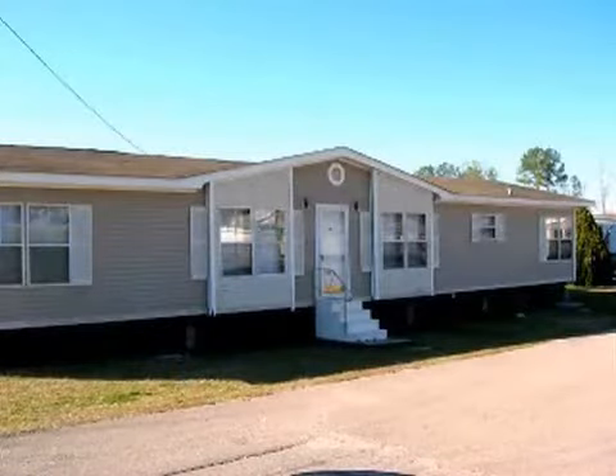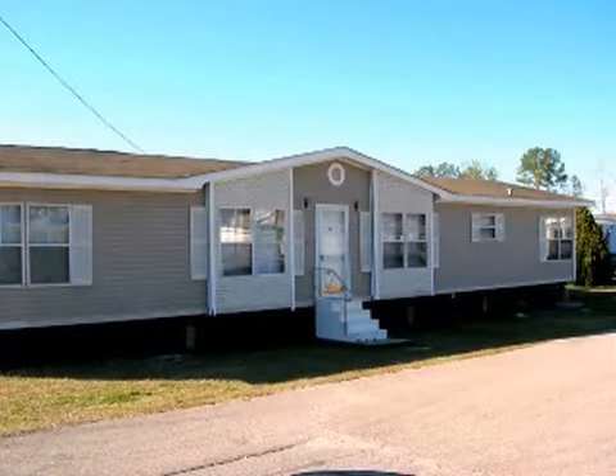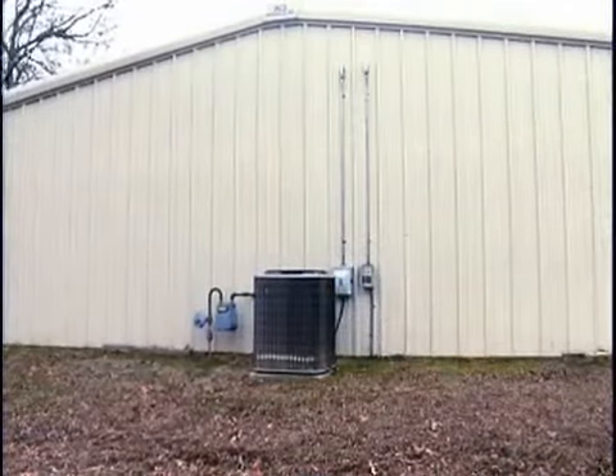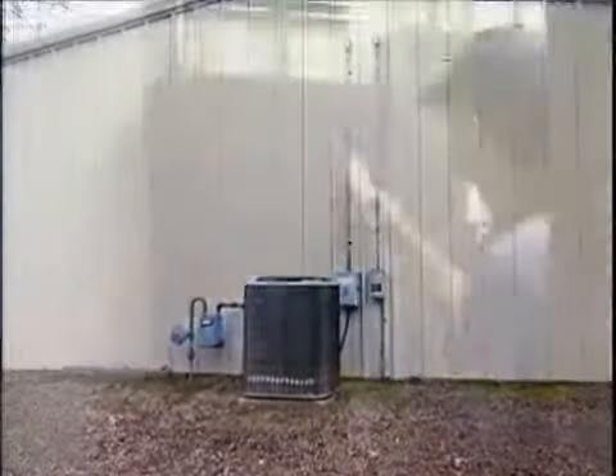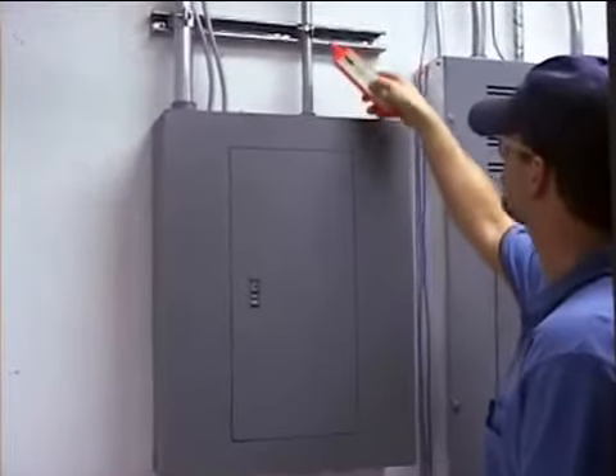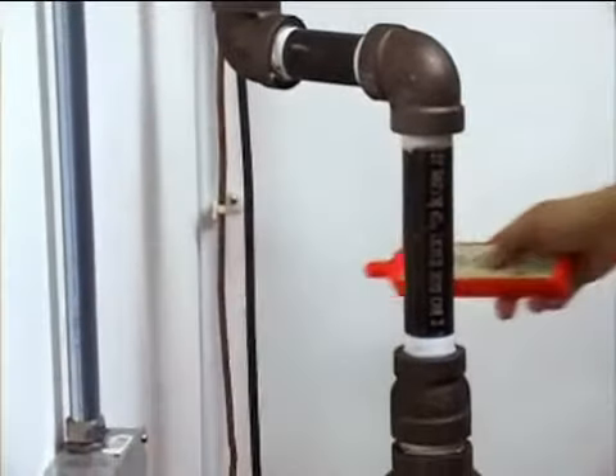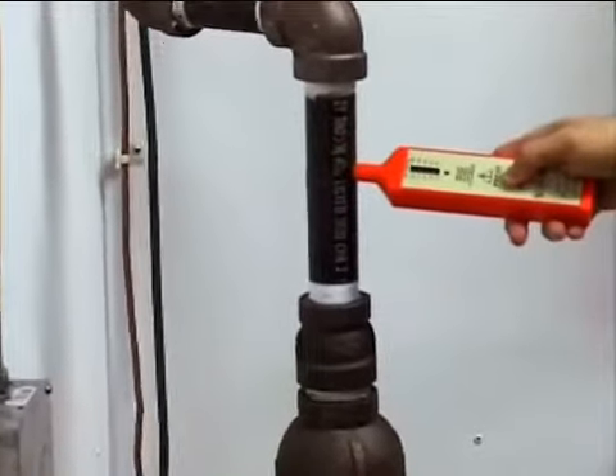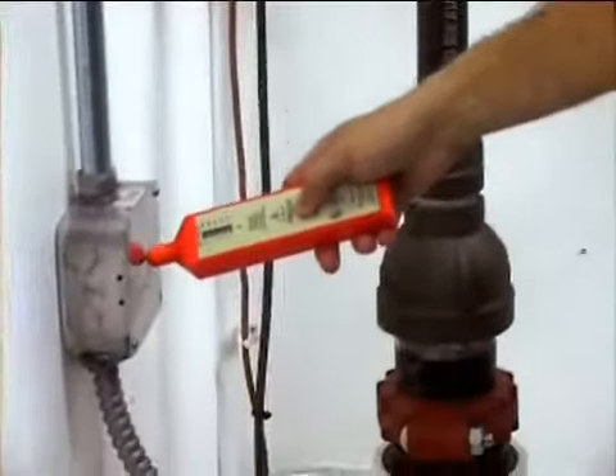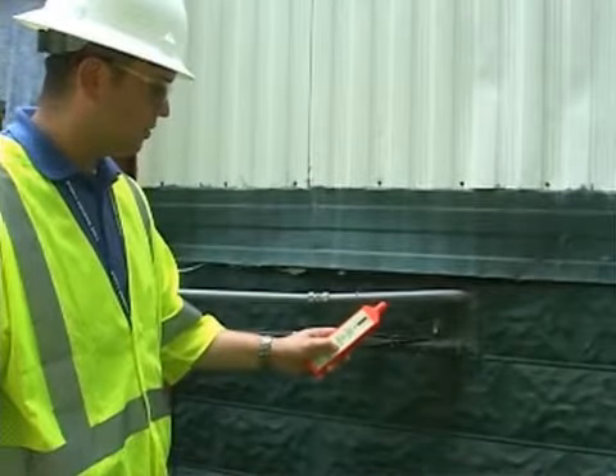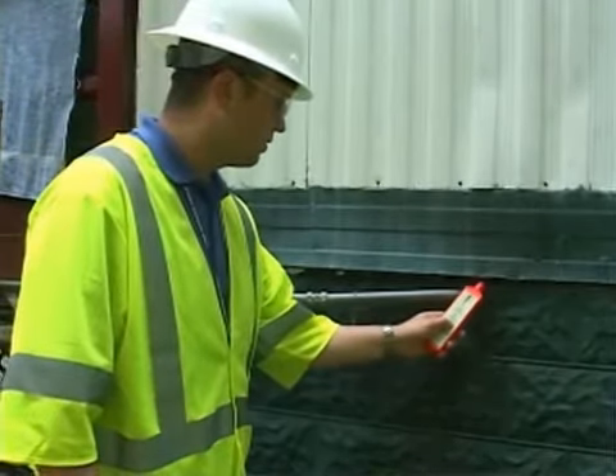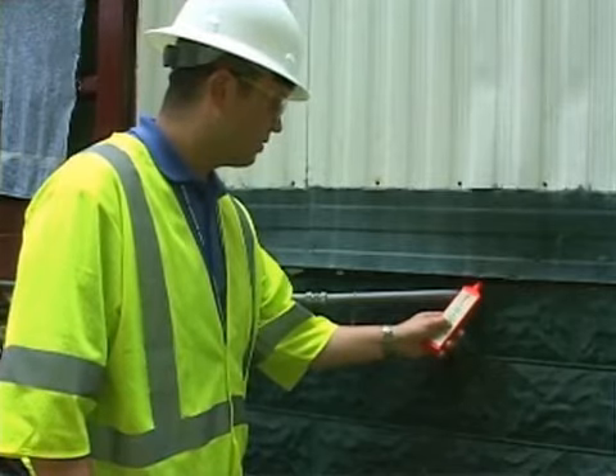It should be noted that any facility such as this mobile home, a metal building, metal conduit, virtually any conductive surface that should be grounded should not read any AC voltage. If any AC voltage is detected, the grounding of the facility should be suspect. This mobile home has been purposely energized, as could happen in the case of a power fault within the structure.